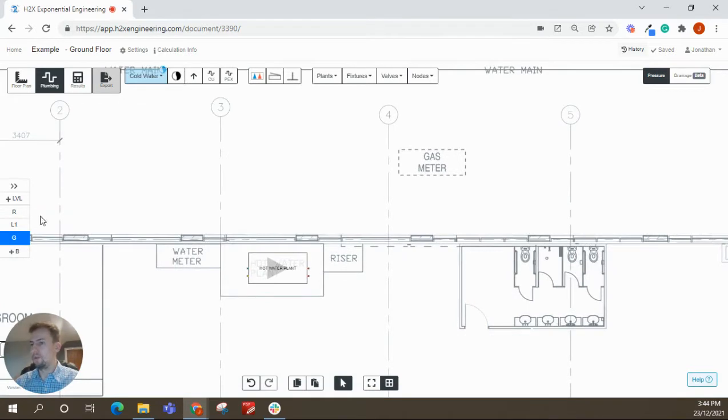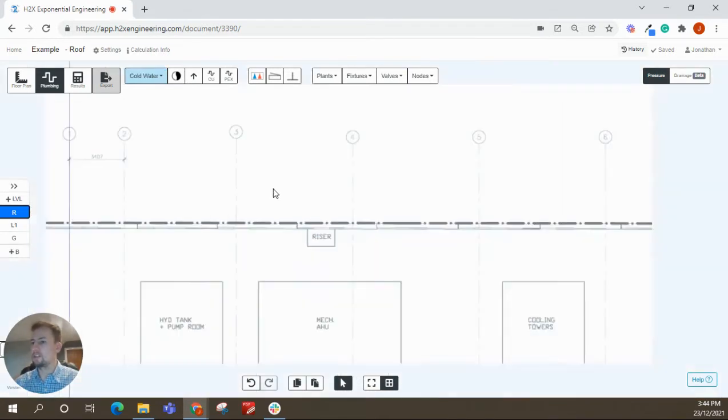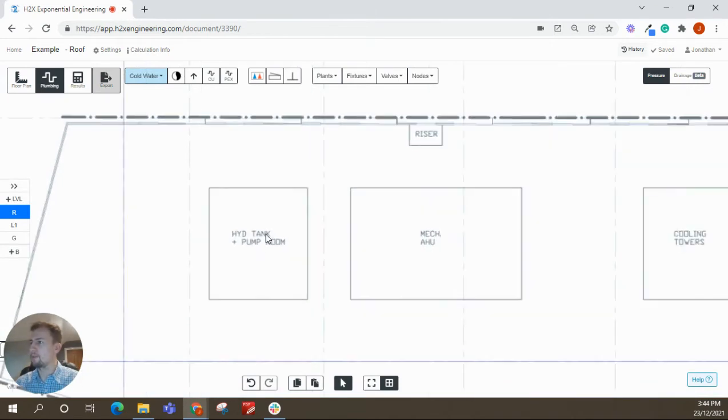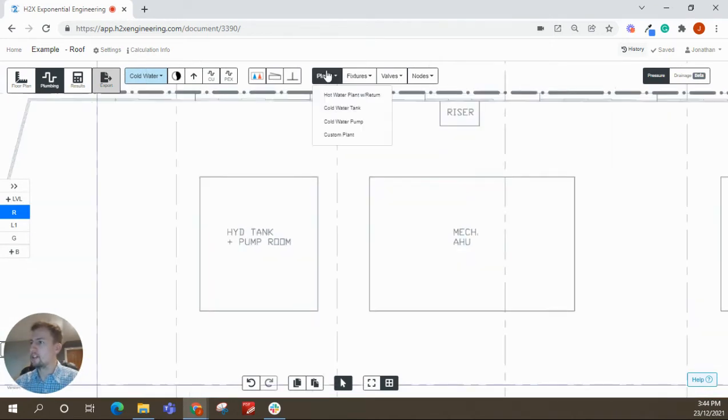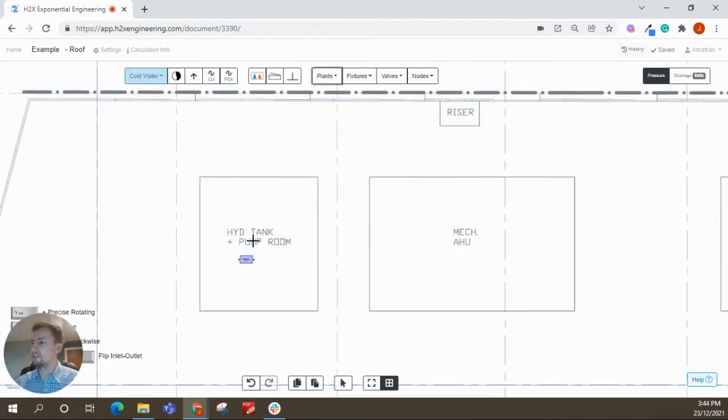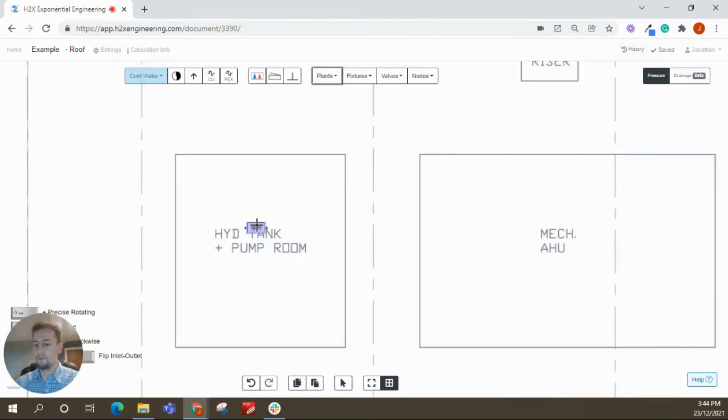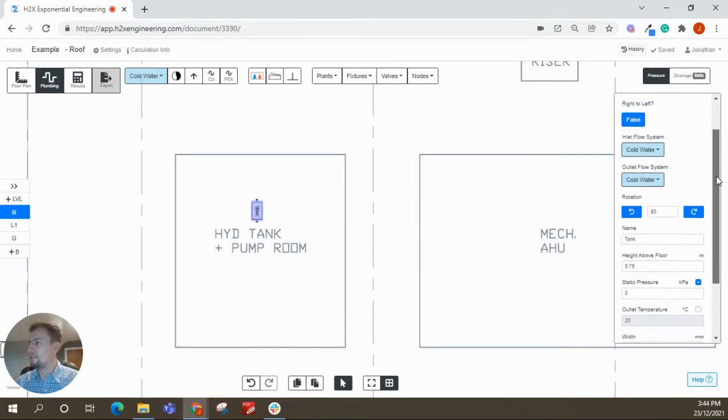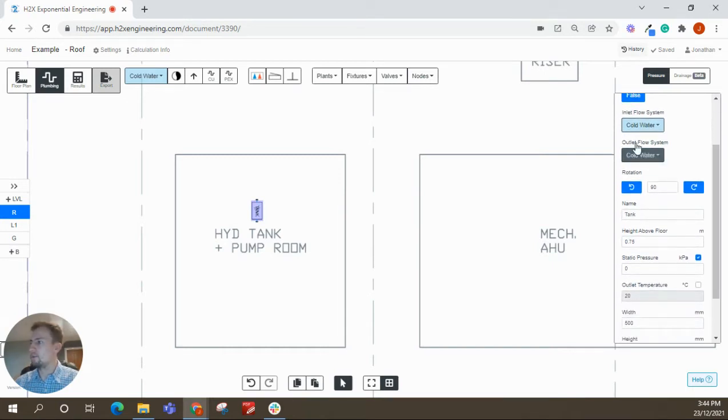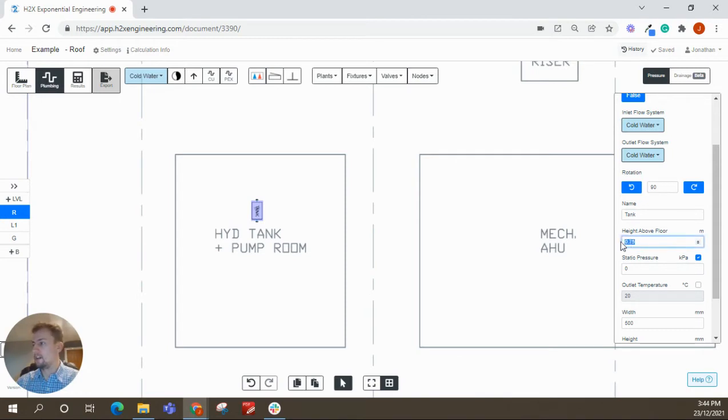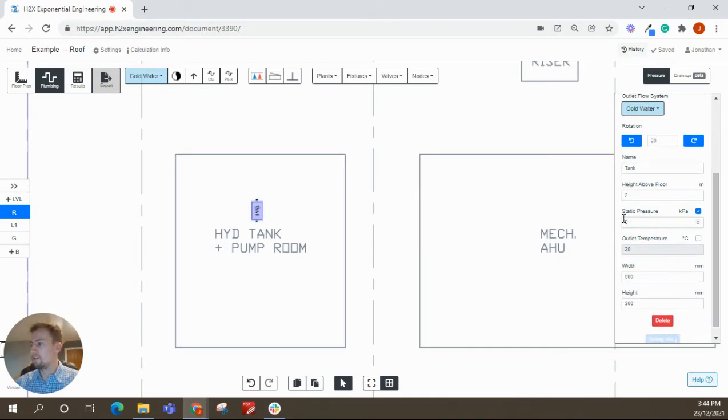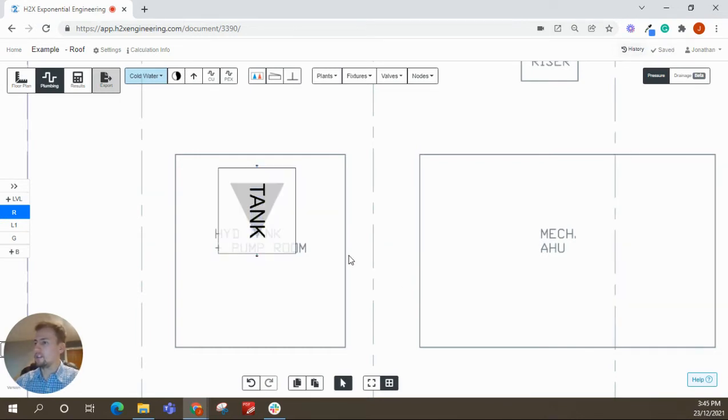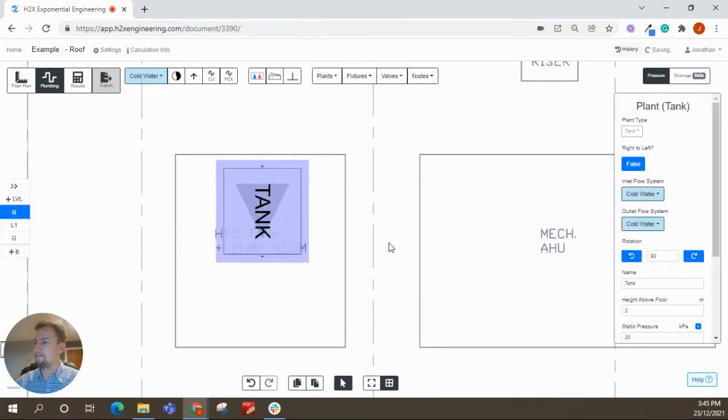But yeah, next, so we've got the hot water plant there. So I know there is, on the roof here, we've got a tank and a pump room as well. So coming back to this drop-down menu, select the tank, and we can rotate that with the arrows on the keyboard. And you've got very similar properties. So what you want on the inlet, what you want on the outlet, change the name. Again, change the height. It brings the pressure to zero. If you want to add a little bit more pressure, maybe there's like 20 KPA for the two meters of height, you can do. And then you have to change the dimensions as well.